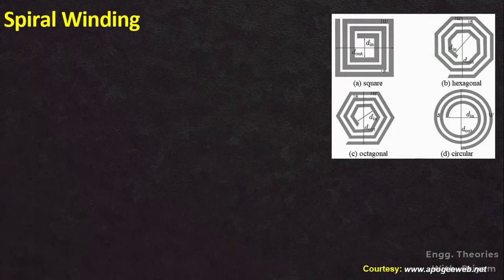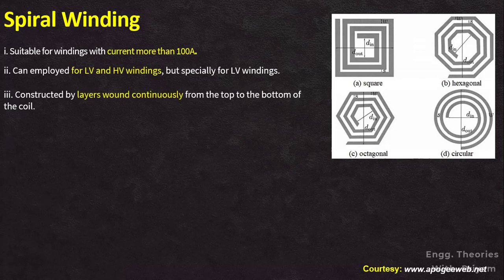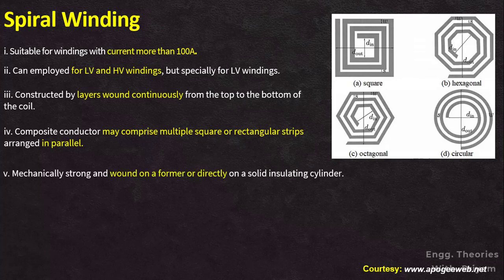The first type of winding used in transformers is spiral winding. It is only suitable for windings that carry currents more than 100 amperes. Typically it is employed for LV windings, but it can also serve for HV windings in cases where the winding needs to carry a current exceeding 100 amperes. The spiral coils are typically wound continuously from the top to the bottom of the coil, and the composite conductor may comprise multiple square or rectangular strips arranged in parallel.